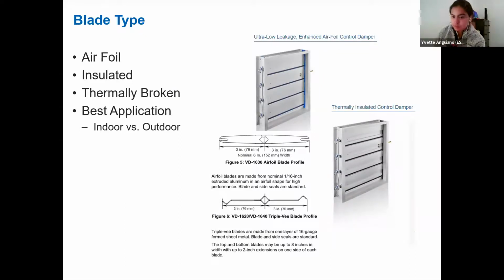So you'd want to use this in more of a coil freeze up concern, such as in air handling units. And then the next step up above that is the thermally broken blade, which again is that same insulated blade type, but in addition to just the blade being insulated, the frame is also insulated. And so the frame is thermally broken with that polyurethane resin along the frame. And then in terms of whether it's best for indoor or outdoor application, you'd want to use that insulated frame where coil freeze up is a concern.